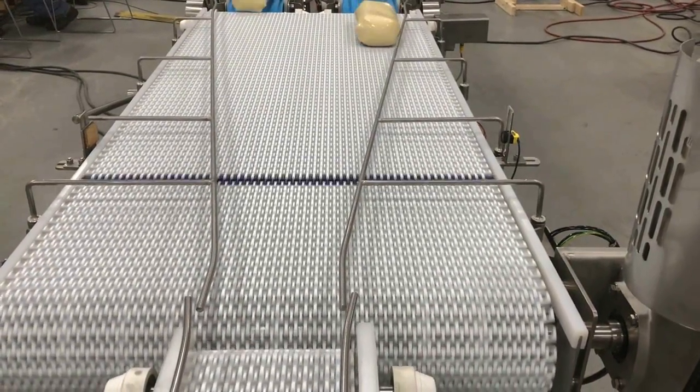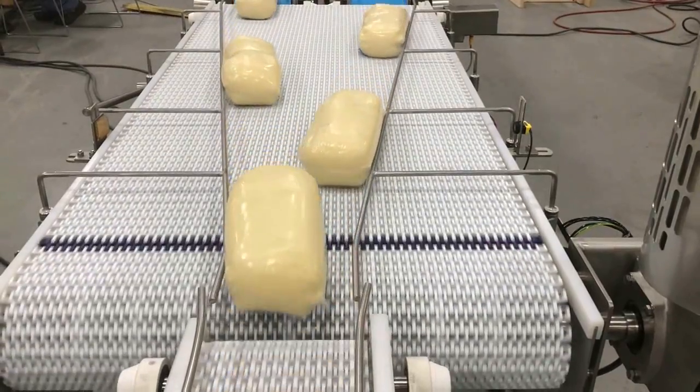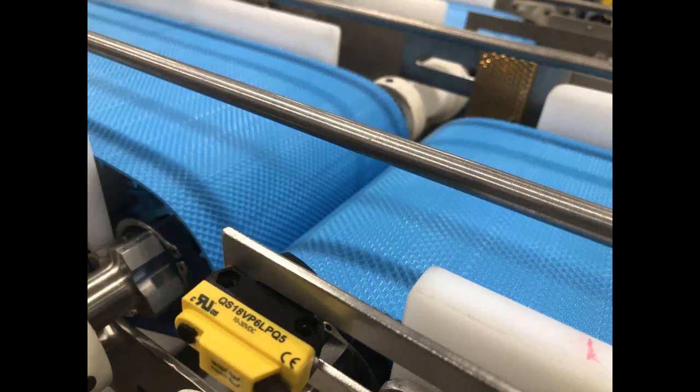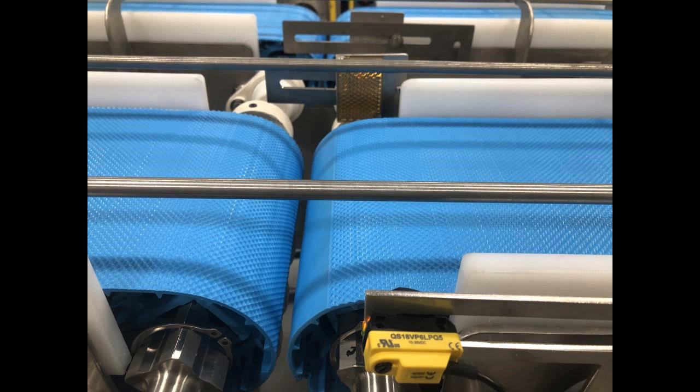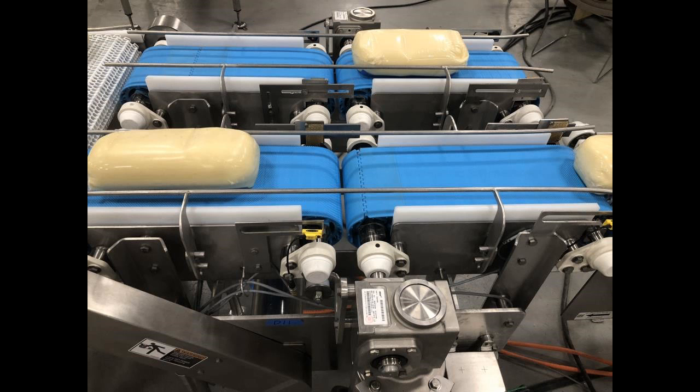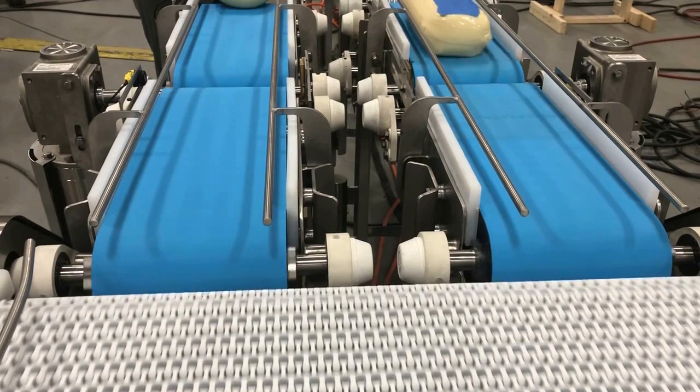To resolve the issue, our experienced electrical team incorporated a combination of pulse and photo-eye sensors, CompactLogix processor, PowerFlex 525 drives, servo motor controllers, and VFDs to develop a new merge concept solution that alleviated big gaps between the product while allowing for more consistent spacing.